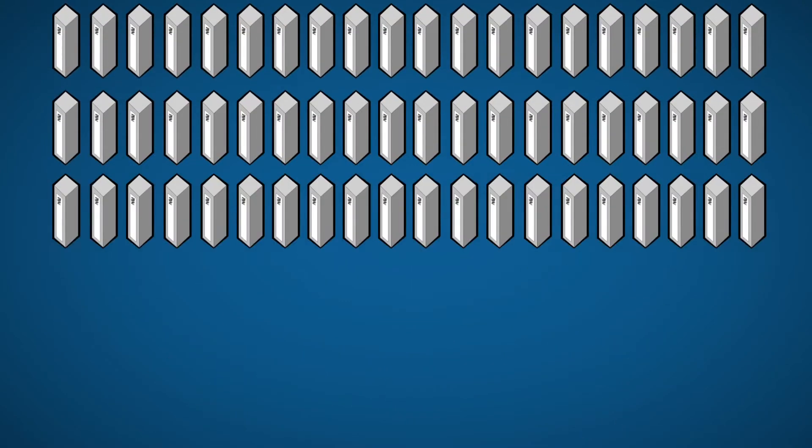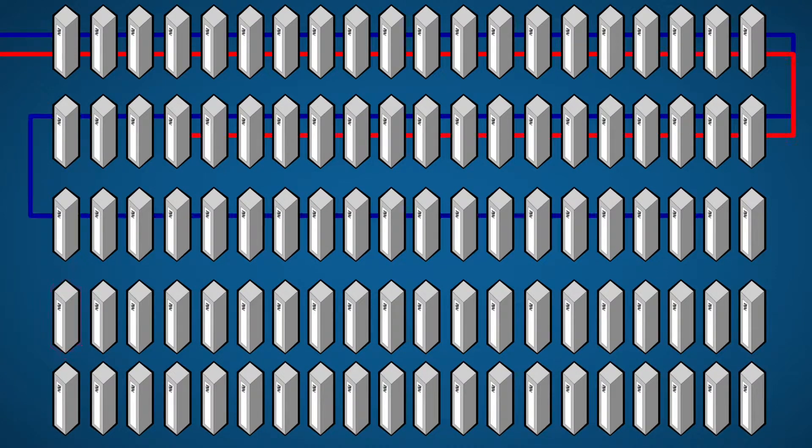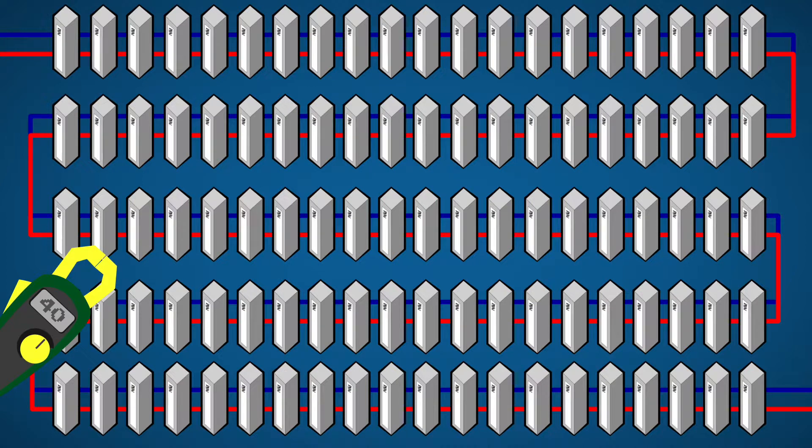Using our same example, at the 61st decoder down the path, our reading before the decoder should be 100 mA minus 60 or 40 mA.